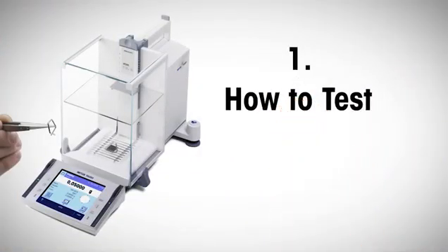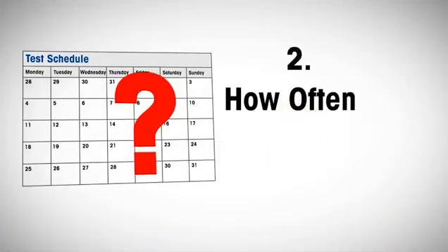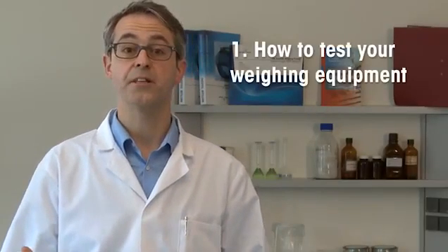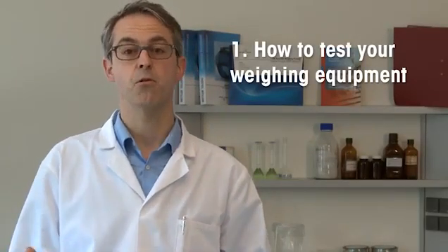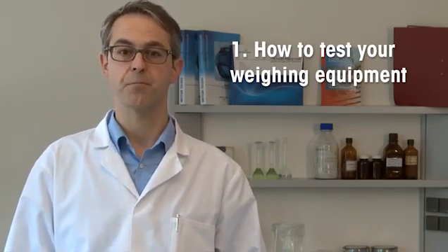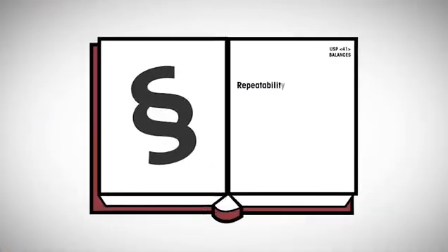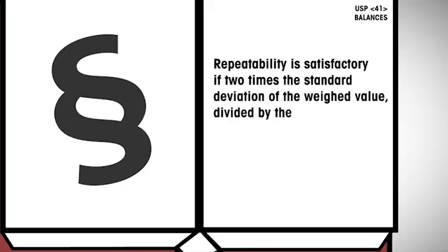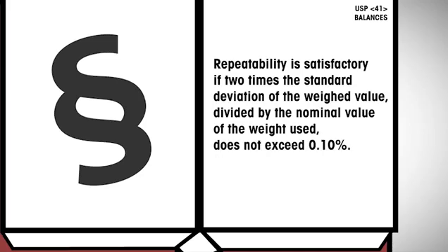How to test the weighing equipment, how often to test it, and how to avoid weighing errors. Probably you are already acquainted with the repeatability test of the old General Chapter 41 weights and balances. Here comes the new chapter with a few small changes. Repeatability is satisfactory if two times the standard deviation of the weighed value, divided by the nominal value of the weight used, does not exceed 0.10%.